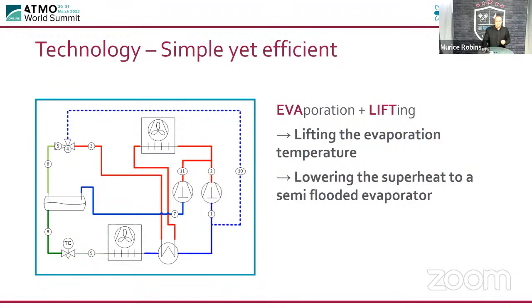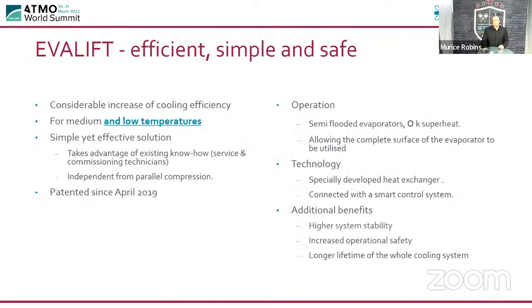Mechanics and service technicians are scared to lower that, because we all know what happens if we have a low superheat on an evaporator. We end up having flooding back to the compressor, damage, oil damage, foaming of the oil, which creates damage on the bearings and so on. So we have to keep that superheat high or higher to make sure that we don't have any issues. But with EVALIFT, we don't have to worry about that problem going forward.